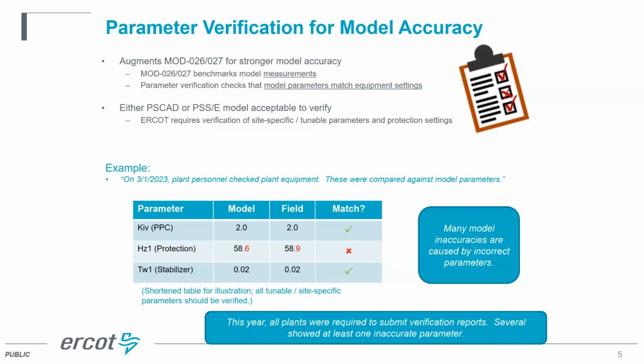This by far has been one of our most successful efforts. This year we required all generators to submit verification reports, and a lot of them found that their models had at least one parameter that was not correct. They were checking the model parameters against the protection settings in the field and whatnot, and found mismatches. So a lot of generators are having to update their models—IBRs and conventional thermal generators alike—because of this exercise.